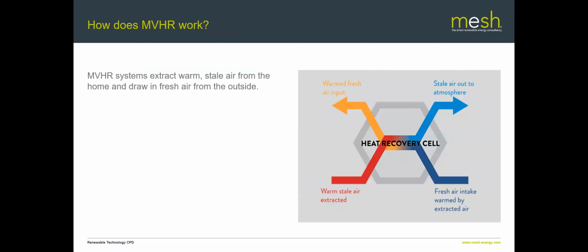So how does it actually work? Well, basically you have a heat exchanger. The two air paths never come into physical contact with each other, so there is no mixing of the stale air and the fresh air, but they go through a heat exchanger inside a box, and that box has a couple of fans in it, and those fans can be controlled to deliver the correct amount of extraction and supply. And the idea is that you balance the extraction and the supply together, and that gives you the greatest possible efficiency.